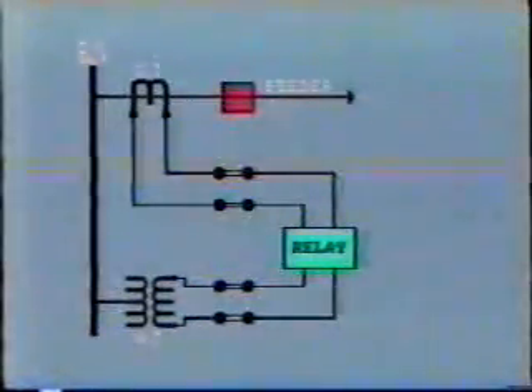Relays are often tested in place by secondary injection. In this test, source input to the relay from CTs and VTs is isolated, and instead, AC current and voltage, where required, is injected into the relay to simulate fault conditions. In some cases, relays are removed from the panel and secondary injection tests performed on the workbench.